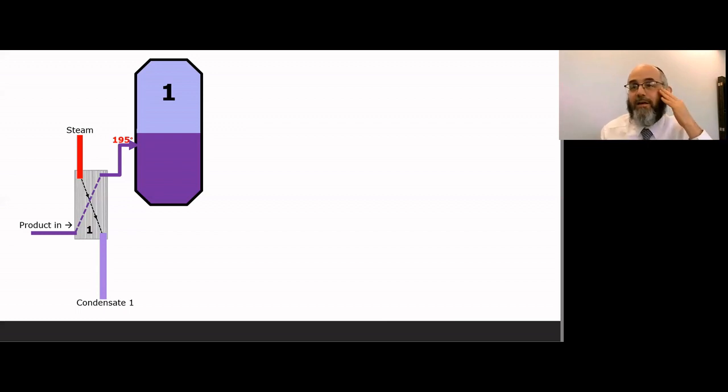You're saying that it's already separating while it's going through the heat exchanger? No. In here, it's just heating up. There's no vacuum for the water to escape. There's no vacuum in the heat exchanger. But when it gets into the effect, there is a vacuum. So when there's vacuum in the effect and the juice is already past 195 degrees, when it hits there, it starts boiling.